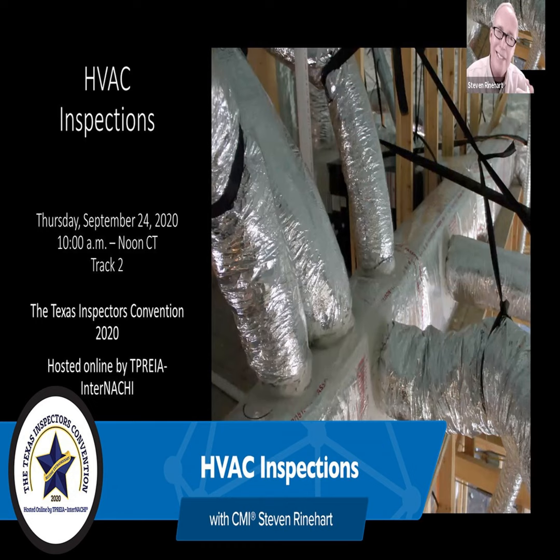This house probably has old, rigid ductwork that wasn't even sealed. When you do that, the house is in a low pressure mode. It's depressurizing because this air handler is mechanically sending air out. And when you depressurize the house, it wants to try to balance itself, and it'll balance itself with any openings.